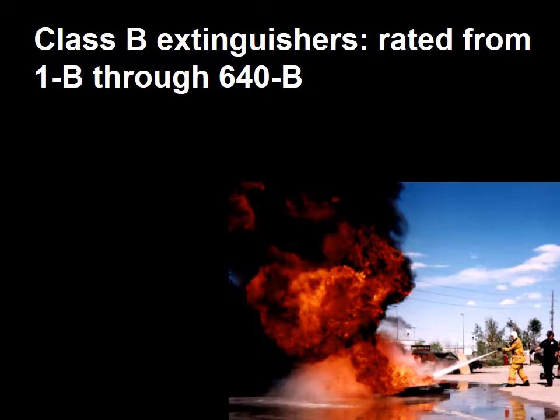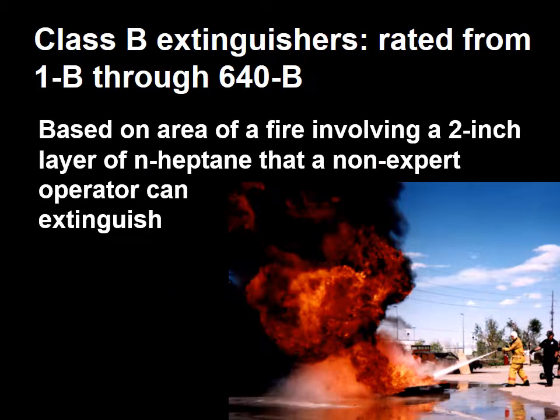Class B extinguishers are rated from 1B to 640B, based on an area of fire involvement in a 2-inch layer of heptane that a non-expert operator can extinguish. Every 1B rating corresponds to 1 square foot of flammable liquid.